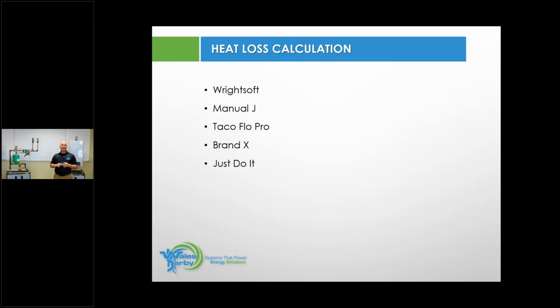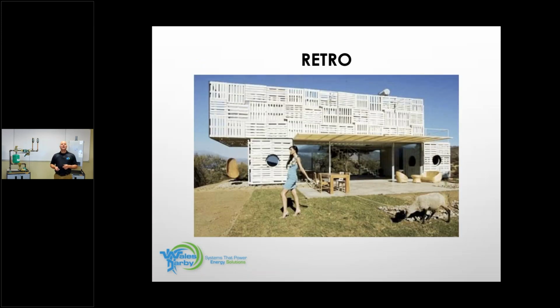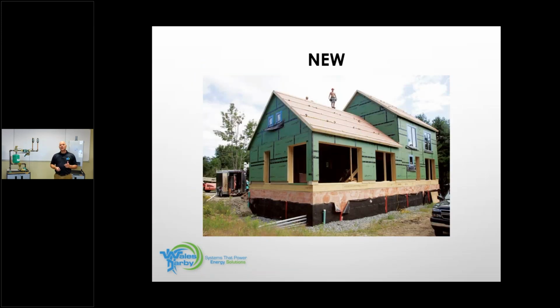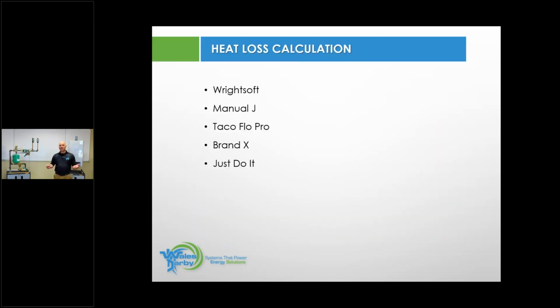We need to do some type of heat loss calculation. Obviously, the heat loss in this home is going to be substantial. After talking with Bob the builder, you'll know what the heat loss will be, whether it's spray foam or Pink Panther. It doesn't matter, but we need to do a heat load calculation. Wrightsoft, Manual J, we don't care what type it is. We just want to make sure you're doing a heat load calculation, because that's your best tool. The majority of boilers you're going to run into in the field are oversized, and some of them are grossly oversized.